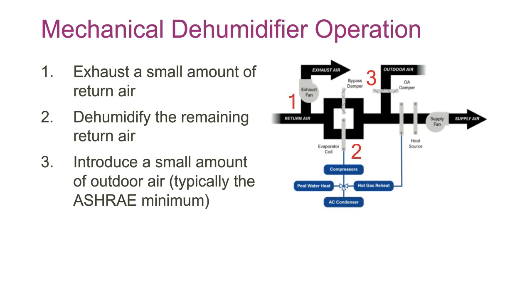You bring the return air back. You can exhaust some air right at the unit on larger systems. Smaller ones might use a separate exhaust fan. You dehumidify the remaining return air, and then after that's done, you introduce a small amount of outside air, typically the ASHRAE suggested minimum, and then reheat it and go to the space.